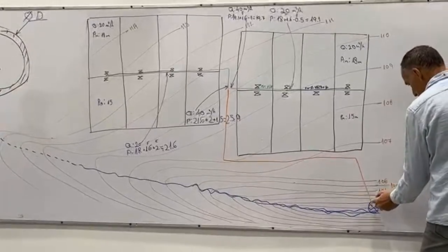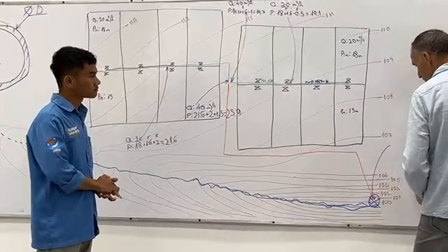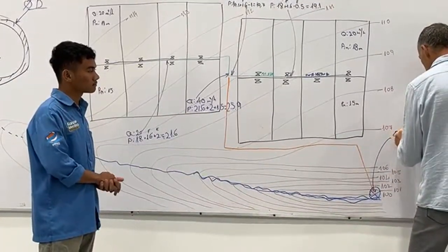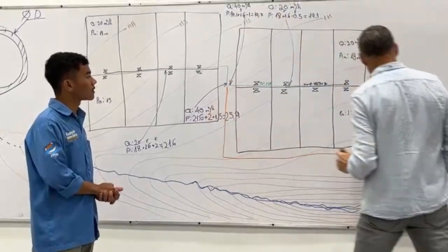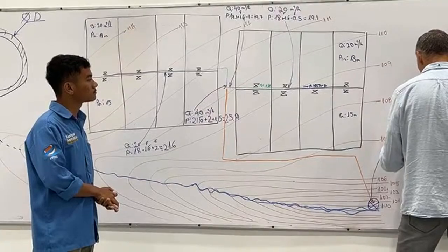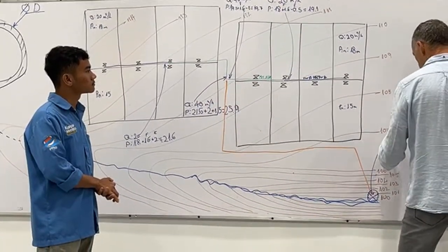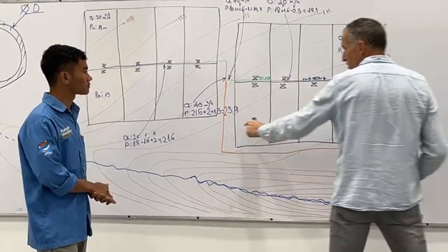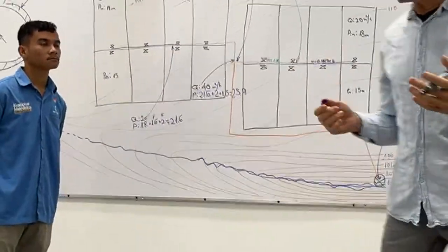Let's find out what's my situation here. So Q is 80 cubic meter per hour, because it's 40 here and 40 here. Yes. 80 cubic meter per hour. P. I start with 25.9. Do you allow me to round it to 26? So it will be here.